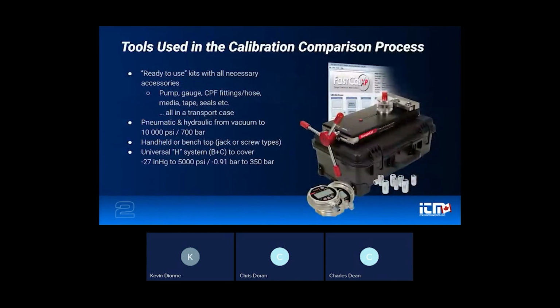Building on the idea of calibration as a controlled comparison process, the next piece is how pressure is actually applied and measured during that process. On your screen, you see a typical calibration setup. This usually includes pressure generation and pressure measurement as separate functions. A calibration pump is used to apply and control pressure, while a measurement instrument is used to accurately quantify that pressure at different test points in order to calibrate your instrument.